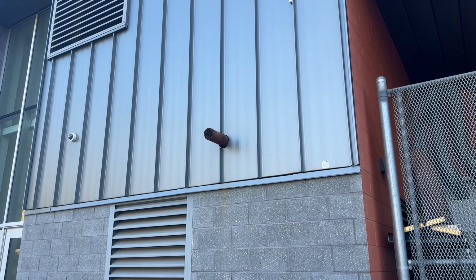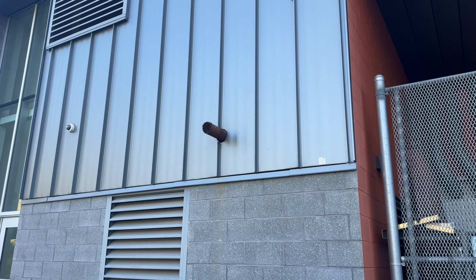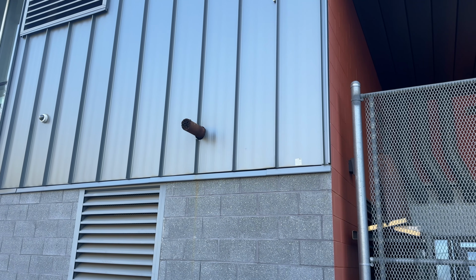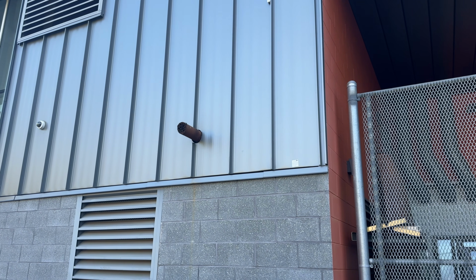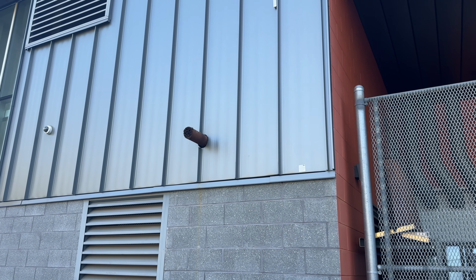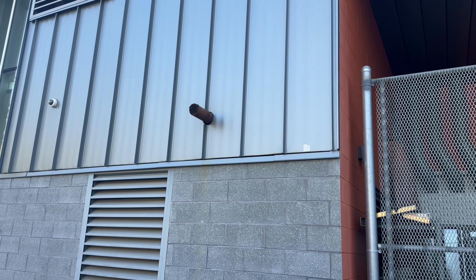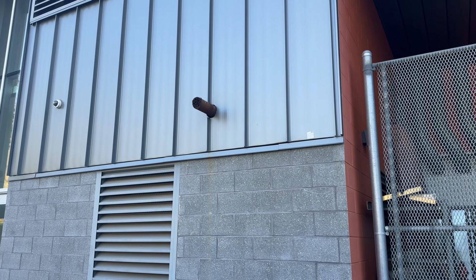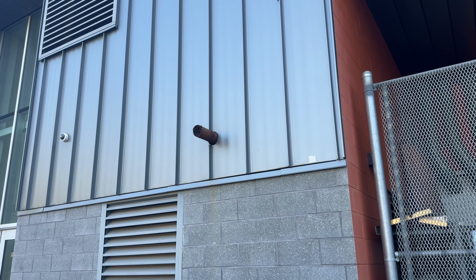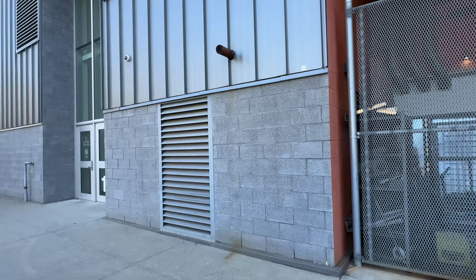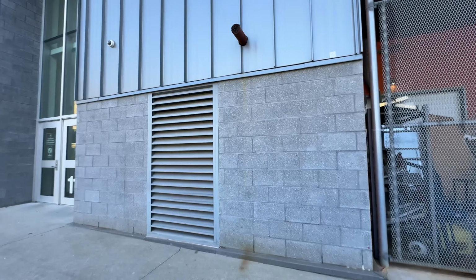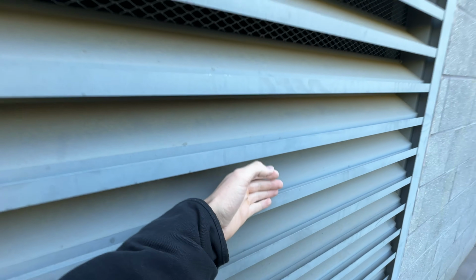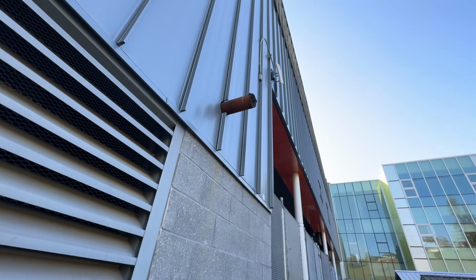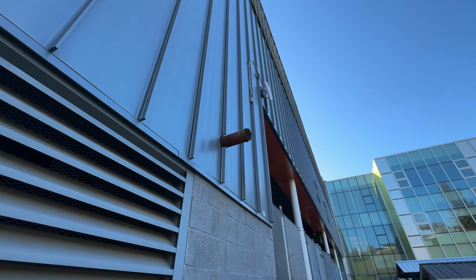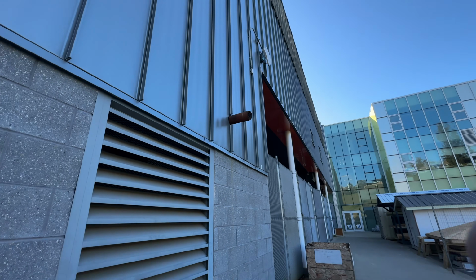I don't think we've got any going on here, as the exhaust looks pretty clear. However, this is now April anyways, so we're getting into spring, and every summer these get run at 100% load for 2 hours, so that'll burn any of that off. So that's good for them to run hard like that. Feel warm air over the radiator, and then very hot air up there. Ask my friend about that one. He can tell you all about how hot that is.